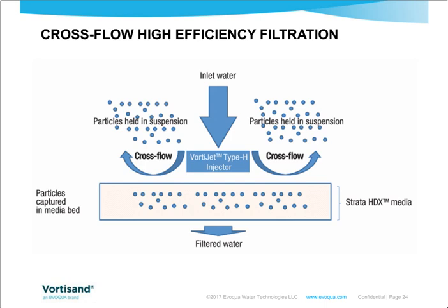The media bed, which we call Strata HDX media, is very small in depth, which is a reduction in the size of the filter, but it also reduces the amount of backwash water required to backwash the filter. We remove those fine particulates out of the media bed, as well as those large particles that are in suspension. We remove that in the backwash from the filter. We typically see an 80% reduction in backwash flows, and we're able to drastically reduce the size of the filter compared to other multimedia filters.